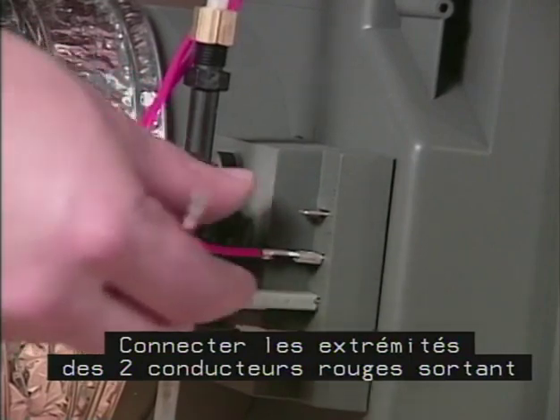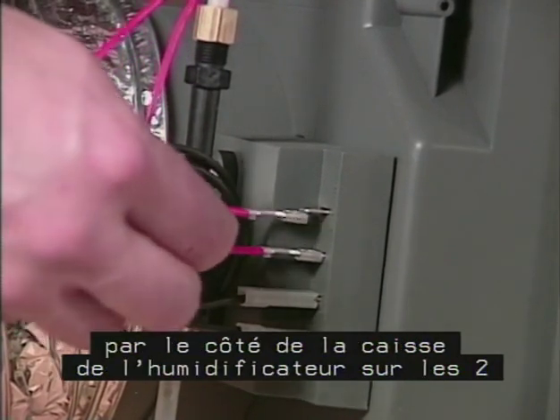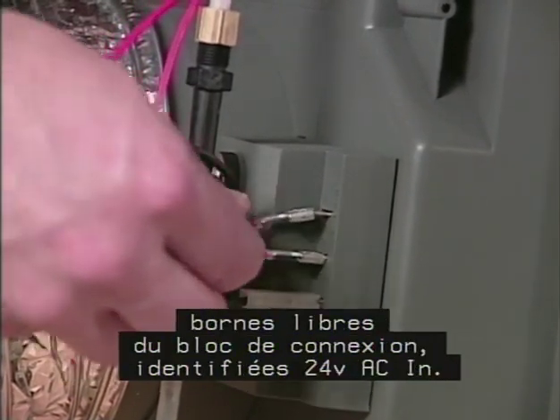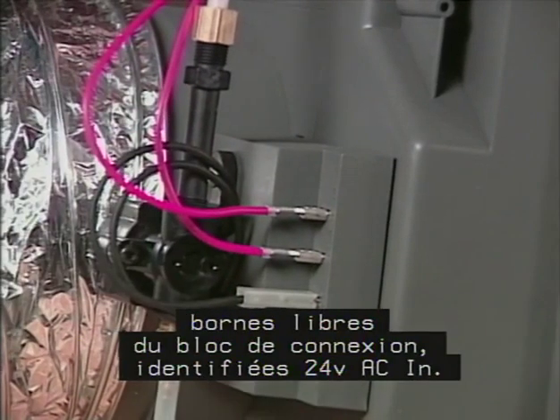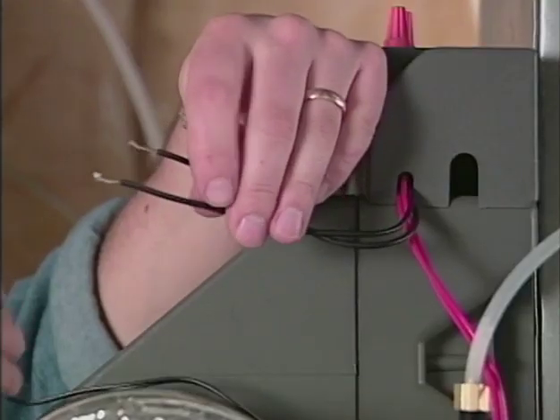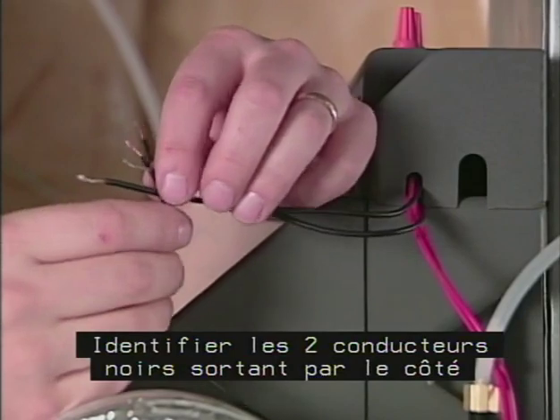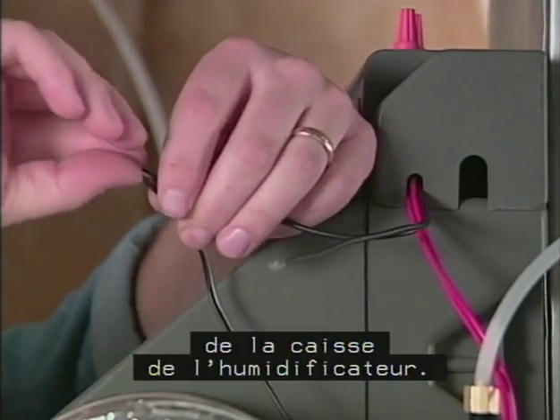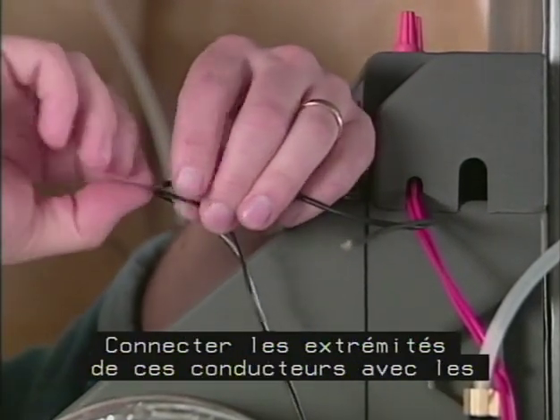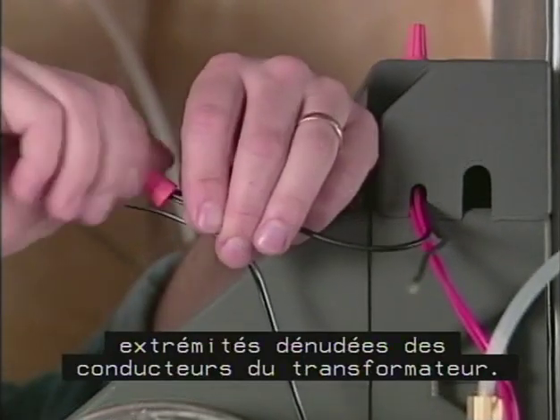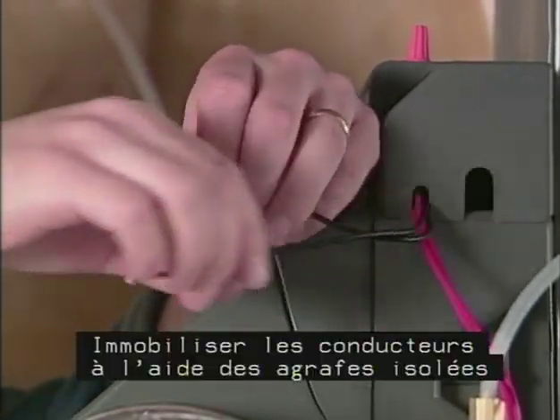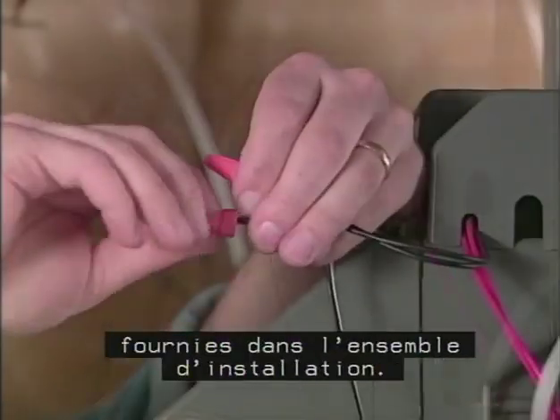Connect the two ends of the red wires extending from the side of the humidifier cabinet to the two free terminals on the terminal block labeled 24-volt AC in. Locate the two black wires extending from the side of the humidifier cabinet. Connect the ends of these wires to the stripped ends of the transformer lead wires. Use the insulated staples included in your installation package to secure any loose wiring.